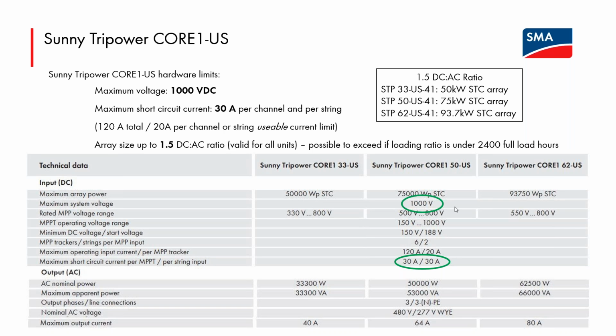And we actually have customers, this methodology for exceeding the data sheet DC to AC ratio is the same for our Sunny Boy residential inverter, our CORE1 commercial inverter, and the PEAK3 utility scale inverter that we'll talk about later. But the CORE1, I think, is the most common that we have customers actually asking about exceeding that DC to AC ratio. And certainly if you were using all 6 of the tracking channels to face an array in different orientations, you could potentially put a very, very large array to the inverter and not suffer much clipping. Or customers may have a situation where there is an AC power limit on their interconnection agreement, but there's no limit on the DC side.